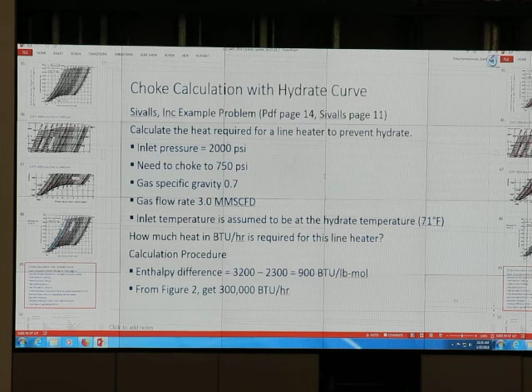For this case, I have an inlet pressure of 2000 psi, and we need to choke it down to 750 psi. Gas gravity is 0.7. Flow rate is 3 million standard cubic feet per day. Inlet temperature is assumed to be 71 Fahrenheit. How much heat in BTU per hour is required for this line heater?